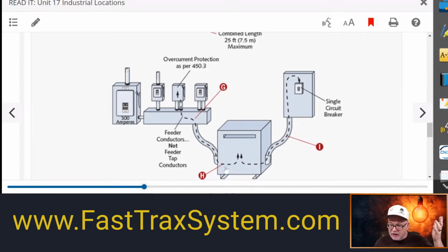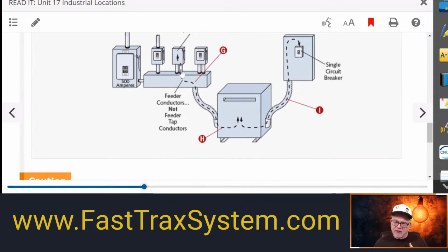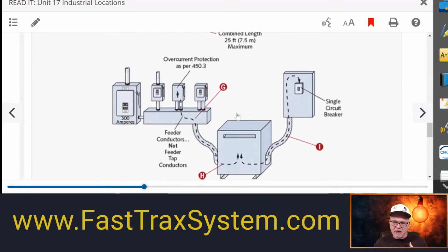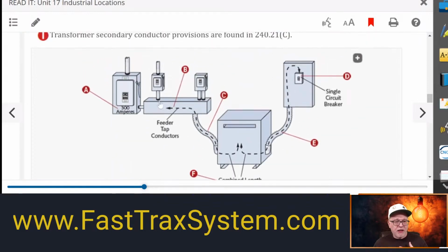And then these conductors right here are not feeder taps. They have to follow the same rules we did earlier, and typically they're going to be sized equal to or greater than the rating of the overcurrent protection that we sized in 450.3(B) for the primary protection. Okay, so I just wanted a distinct difference that this is not considered a feeder tap, so you can't use those rules. Where you're feeding a trough and you're coming out of it, you're tapping actually onto the feed. This, you can utilize feeder tap rules, okay? Make it very clear that's what you're doing, okay?